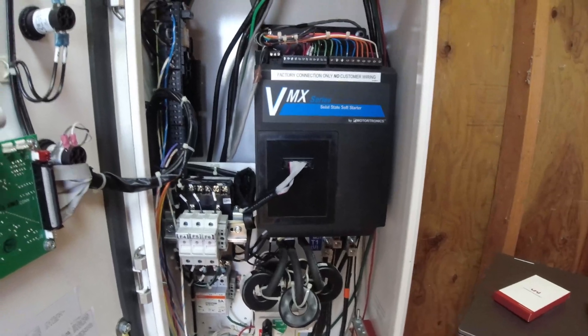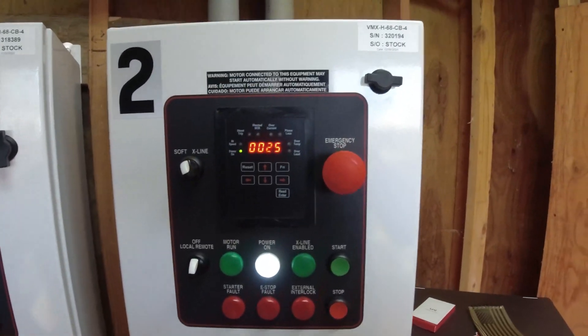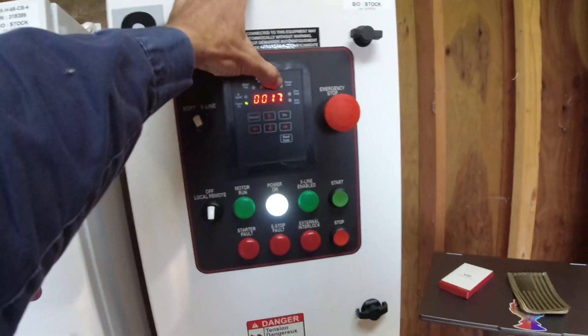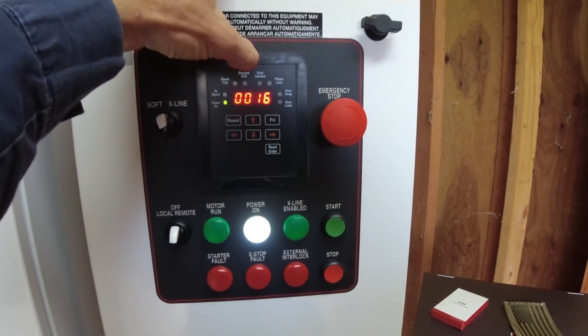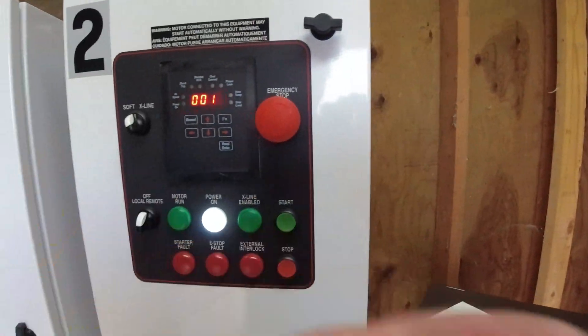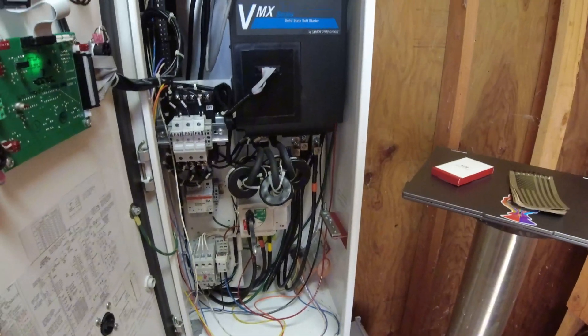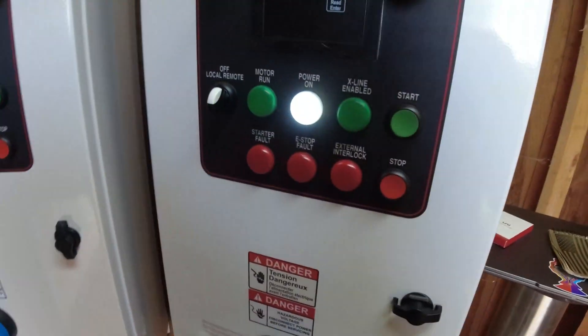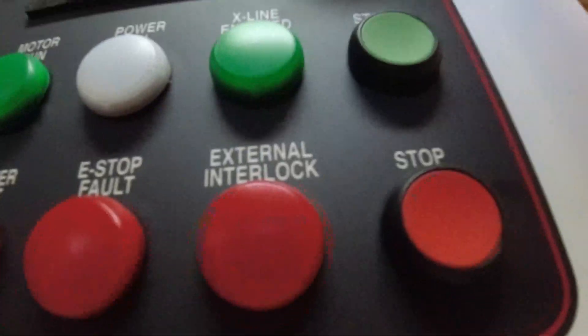That's a bummer, but at least we found the problem. The printed circuit board inside this soft starter is faulty and needs to be replaced. I'll get on the phone with Motortronics in the morning and send an email now to get that moving. We finally caught it misbehaving. We saw on the fault log it was bouncing between 10 and 20 amps while not running - and that's exactly what we're seeing now. This thing is just all over the place. We're shutting off power to it - it's dead until further notice.